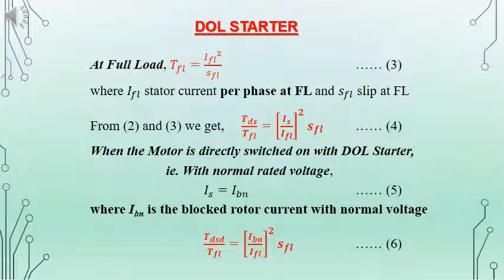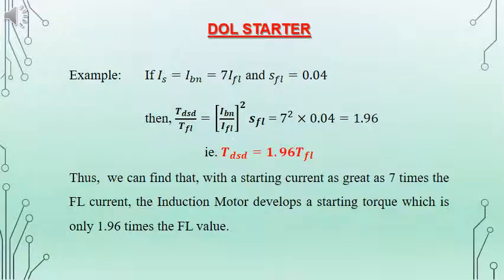So remember the equation TDSD divided by TFL is equal to (IBN divided by IFL) the whole square into SFL. Here we will consider an example where IBN, the starting current in a DOL starter or direct online starter, will be 7 times that of the full load current. If you are directly applying the entire voltage across the stator of a 3-phase induction motor, the current will be 6 to 7 times that of the full load current, and the corresponding full load slip is equal to 0.04, which is very small.